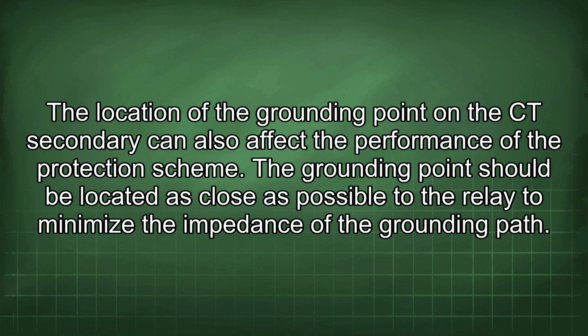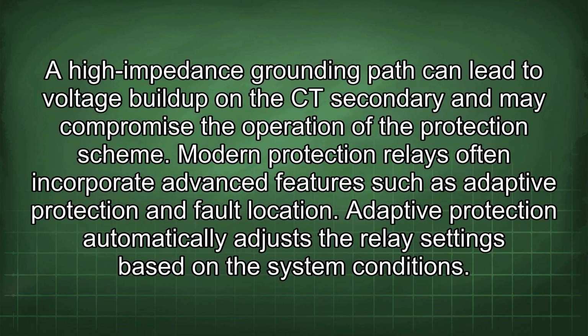The location of the grounding point on the CT secondary can also affect the performance of the protection scheme. The grounding point should be located as close as possible to the relay to minimize the impedance of the grounding path. A high impedance grounding path can lead to voltage buildup on the CT secondary and may compromise the operation of the protection scheme. Modern protection relays often incorporate advanced features such as adaptive protection and fault location.